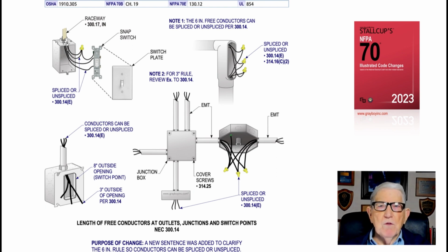And notice that if you measure from the back of the connector there, basically, it's 6 inches. That gives you enough if you need to make a splice on a 6 inch conductor measured in this manner. It also gives you enough conductor length to terminate to a receptacle or to a switch. And then notice the bottom, if you're measuring from the very face of the box, as you see here, then it's 3 inches out. That gives you enough length of conductors to terminate devices, switches, plugs, things like that. And then, as you see to the right, we're just having conductor length so that we can splice. And then notice in an LB, the LB has to be listed and give you the cubic inch rating.